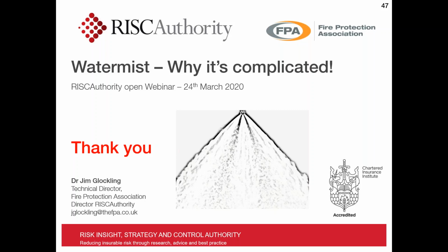Another question: can you talk a little about representative fire tests and how much interpolation you see where tests are not fully representative of the final application? That's a very good question. Certainly, the key factors I would look for in assessing whether fire testing is appropriate to your end application are: ceiling height is a crucial factor, compartment volume is a crucial factor, and ventilation is a crucial factor also. If I then extend that to say that the heat release rate of the fuel and fire size contribute also, I've probably defined all the variables that say testing needs to be fairly bespoke. But I think it's probably time to take quite specialist advice. The larger the compartment size, probably the further away you get from having an assurance that tests are relevant.